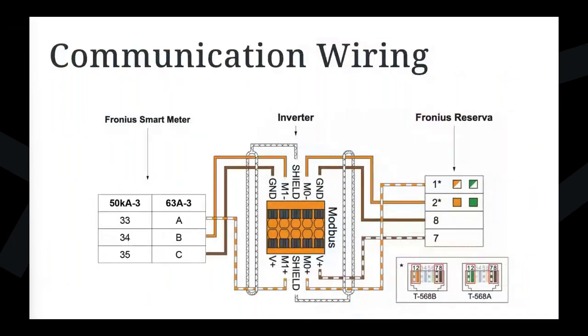In terms of communication wiring, to avoid crimping issues that can happen when you make up your own cables, we strongly recommend using pre-made Cat5 or Cat6 cables with an RJ45 lead. And just note that there are two types of data cables that you can get with different color orders. You can see type A and type B down here at the bottom right. So make sure that you understand the color order that you're using to make the right connection back at the orange communication plug at the inverter.